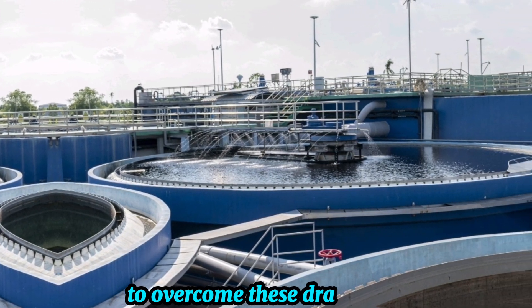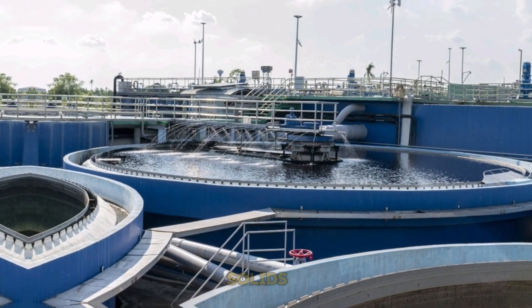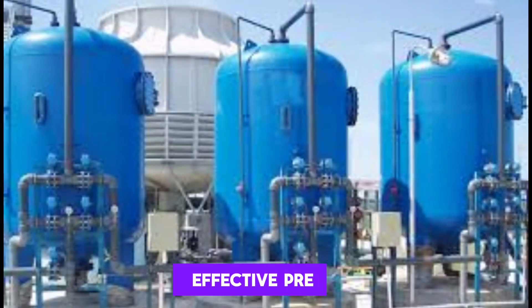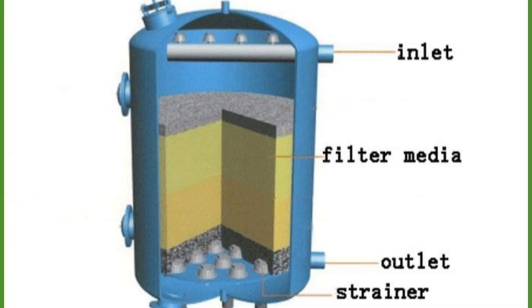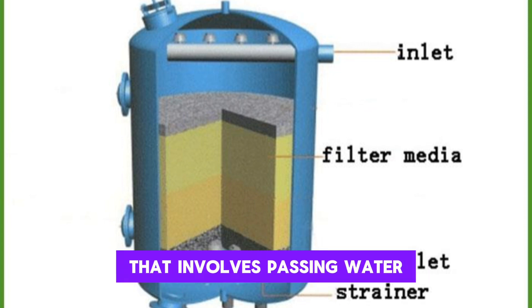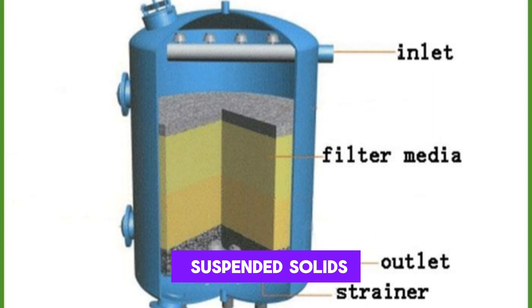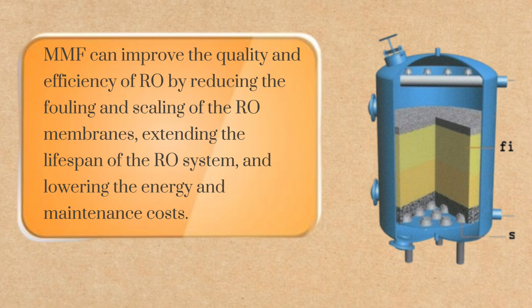To overcome these drawbacks, RO plants often use pre-treatment methods to reduce the level of suspended solids, turbidity, color, and microorganisms in the feedwater. One of the most effective pre-treatment methods is multimedia filtration, MMF. MMF can improve the quality and efficiency of RO by reducing the fouling and scaling of the RO membranes, extending the lifespan of the RO system, and lowering the energy and maintenance costs.